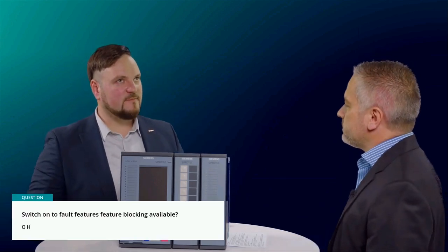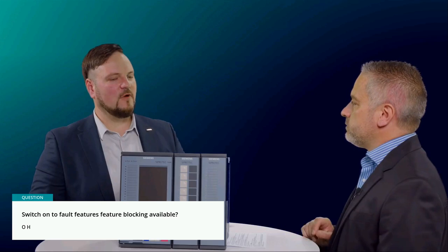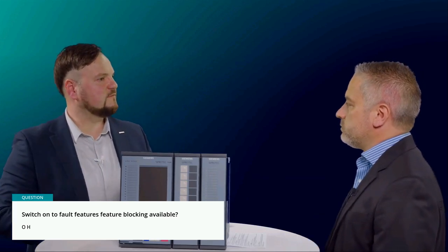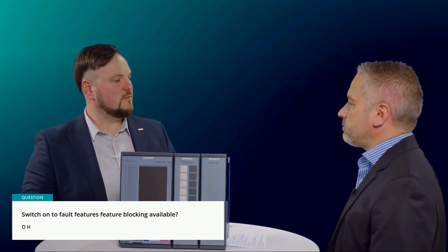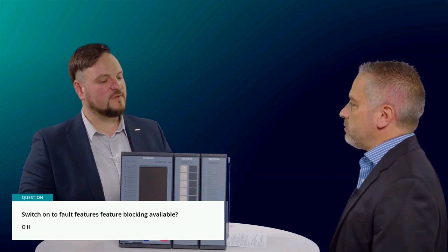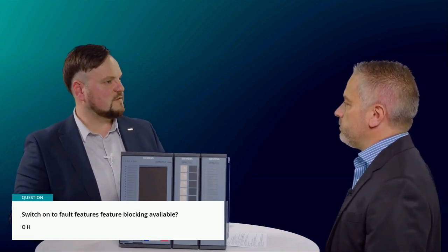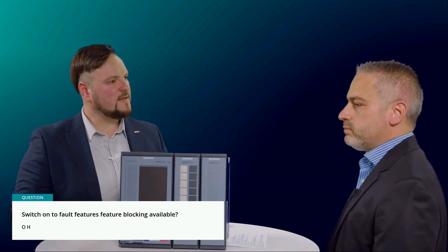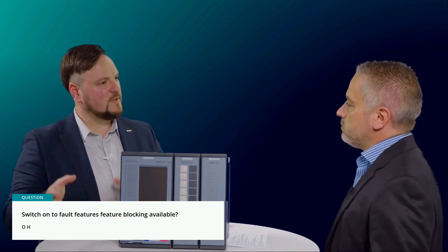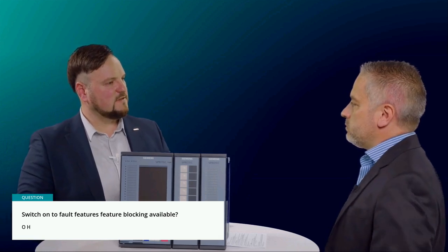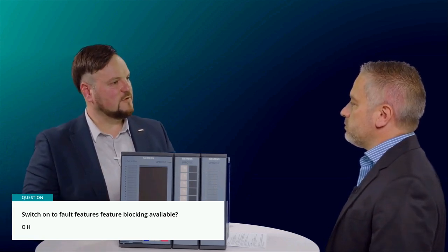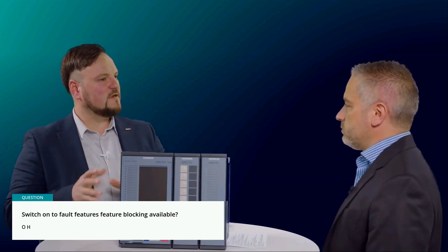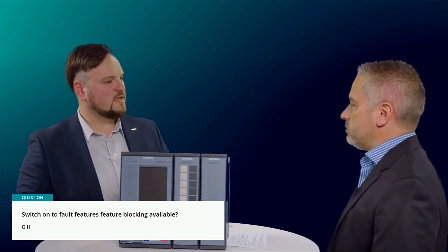Switch onto fault feature - is a blocking feature available? Yes, blocking feature is available. Normally, if you have a fault on the alternative incomer, this incomer is blocked, meaning the HSBT function is not ready to transfer to that incomer. Maybe in a more complicated application, we can provide that the application will transfer to another incomer, but normally if there's a fault on the alternative incomer, we block the HSBT function.